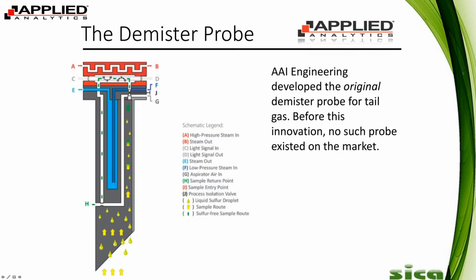So here you see a very nice cutaway of the internals of the Demister Probe. So you can see the bottom of that would be stuck into the process pipe. And you can see the flow path follows those yellow arrows up the probe body. And you can see the blue section, which we call a cold finger. And what the cold finger is doing is dropping the temperature, which allows the sulfur vapor to condense and drop out back into the process pipe. So that's basically how we remove the sulfur vapor.